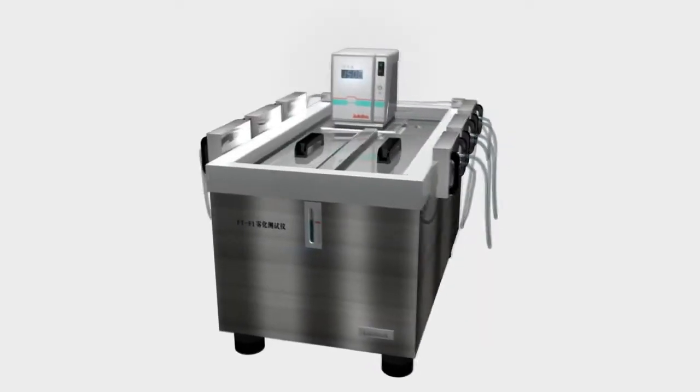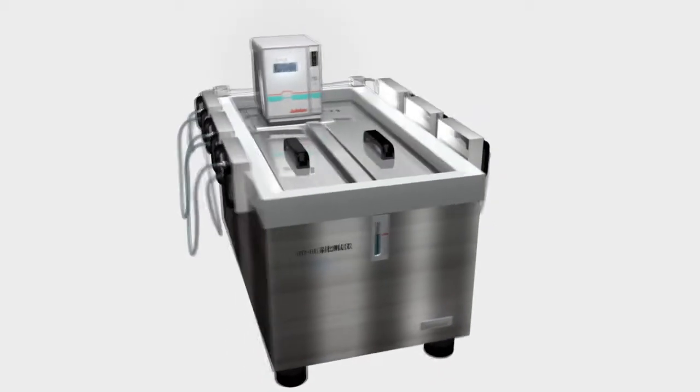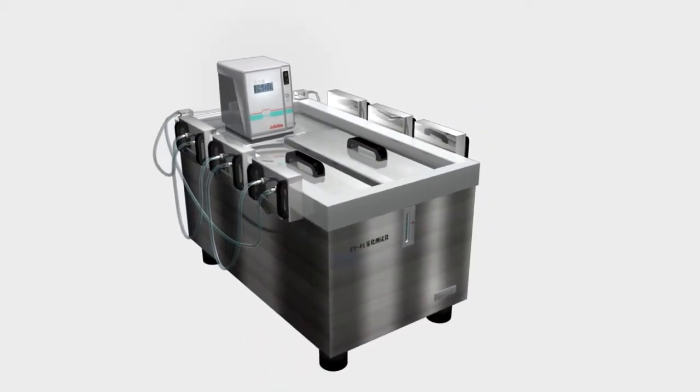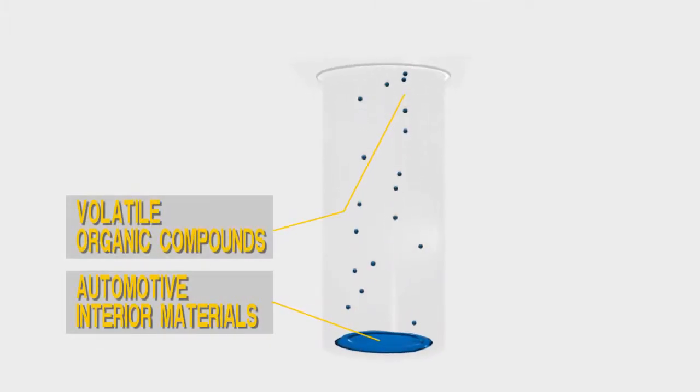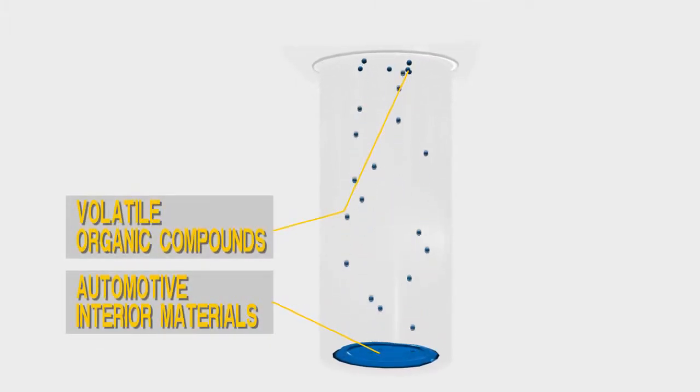By simulating the complete process during which high temperatures accelerate the evaporation of volatile organic compounds in a fixed time, the instrument can determine the material's fogging property to assist material manufacturers in product quality control and inspection.